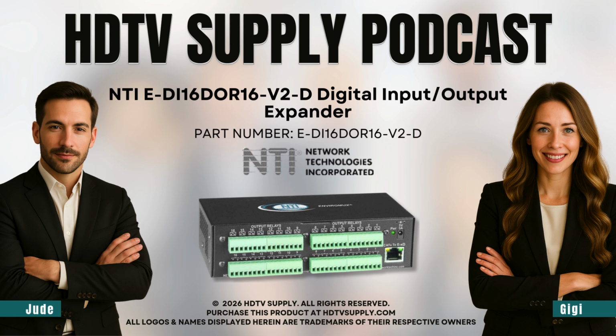Okay, so we get how it reads data. What about the control side, the O in I/O? The output side uses what's called a normally open SPST relay design. SPST, so single pole, single throw. Basically a simple on-off switch. A simple electronic switch, exactly. The NTI system can use it to turn up to 16 external devices on or off. Now, I did see the rating is pretty low, 125 volts AC at half an amp, or 30 volts DC at 1 amp. Is that enough to be useful?